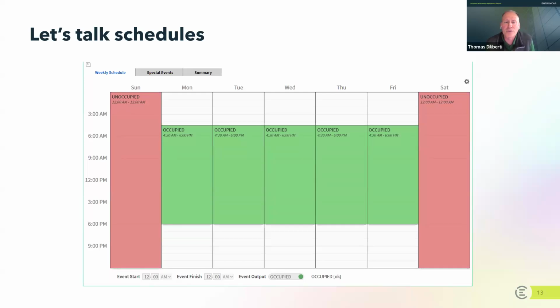Or to say that another way, it will turn the system on earlier on a severe weather day when it's really cold or really hot, and then it will make sure the system is at the right temperature when you get to the time that you're occupied. So it does the math backwards in order to turn itself on. If you have optimal start as part of your system, many times people don't schedule it correctly. If this particular occupied mode includes optimal start, it very likely means the system would be turning on at 4 o'clock or 3:30 or even 3 o'clock in order to get up to temperature in the occupied mode where you want to be.